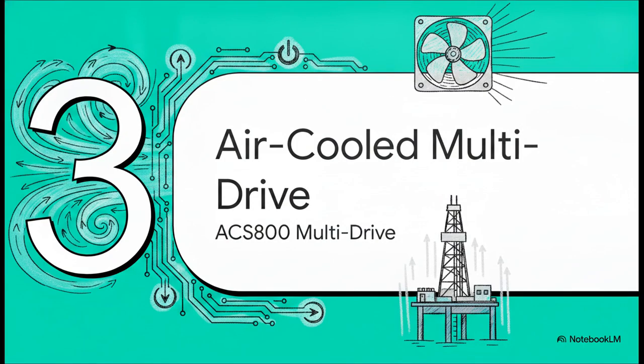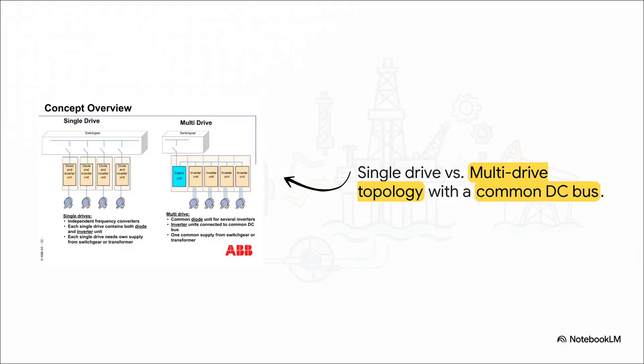Section 3, air-cooled multi-drive. So what if you don't use water cooling? Before we look at the alternative cabinet, we need to quickly recap the architecture. Remember single versus multi-drive topologies? A single drive means every frequency converter has its own diode supply unit, its own inverter, and its own feed from the switchgear. But with a multi-drive topology, you use one common diode supply unit to feed several independent inverters, all hooked up to a common DC bus.